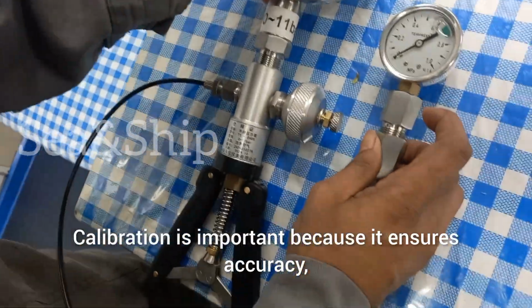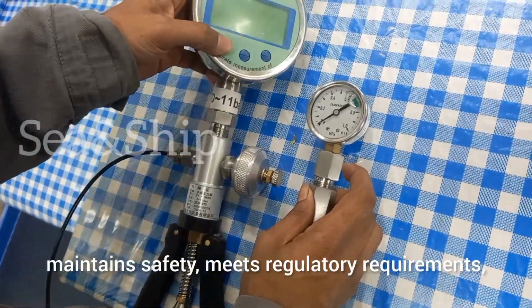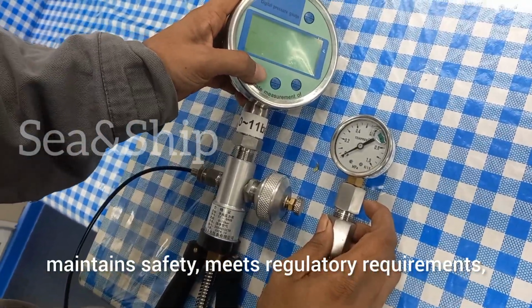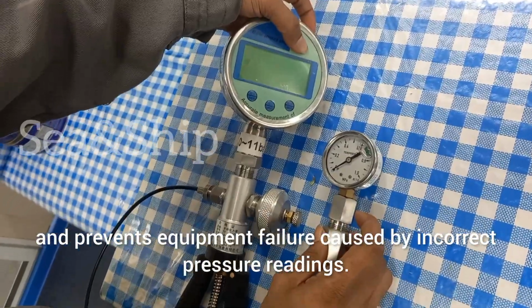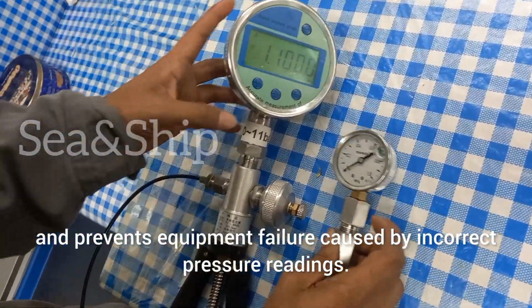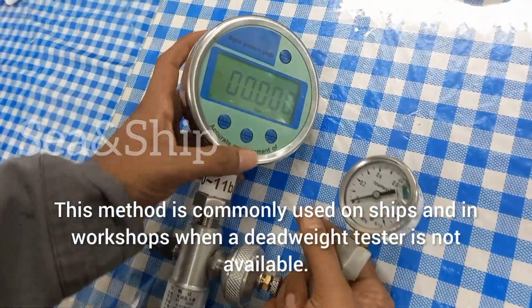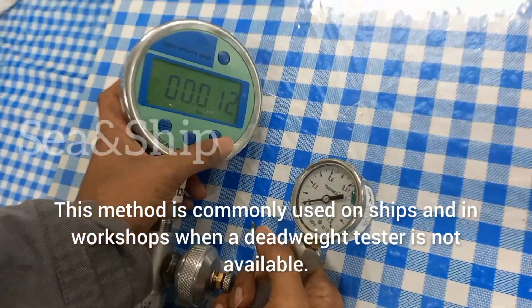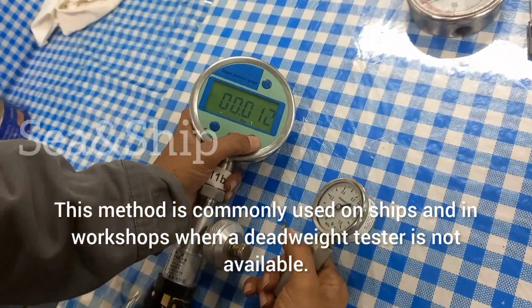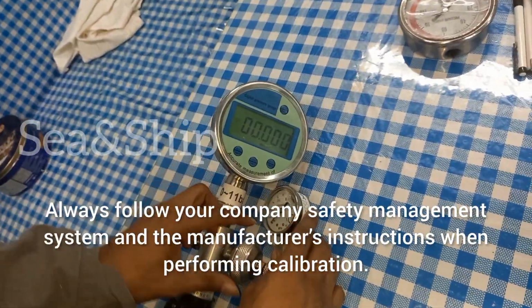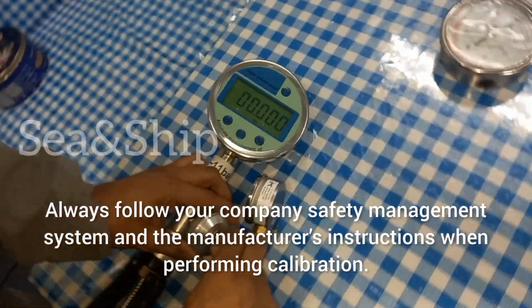Calibration is important because it ensures accuracy, maintains safety, meets regulatory requirements, and prevents equipment failure caused by incorrect pressure readings. This method is commonly used on ships and in workshops when a deadweight tester is not available. Always follow your company safety management system and the manufacturer's instructions when performing calibration.